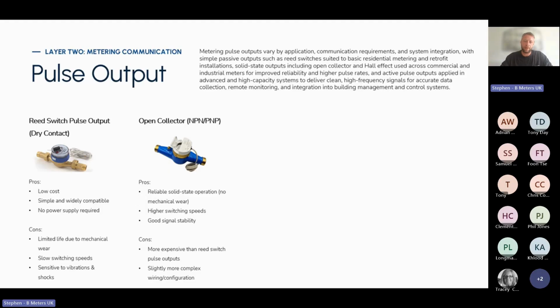More meters that you associate with the utility markets around Europe, such as BMeters, Itron, Elster, where they have a pulse output, it's an open collector pulse output. And the pros of the open collector run in the face of the cons of the reed switch pulse output. Reed switch pulse outputs have limited life due to mechanical wear, slow switching speed, and are sensitive to vibrations and shocks. Ultimately, if data is important, the reed switch pulse output is just not going to cut it long term. It will work, it will serve a purpose, and it's very easy to work with, but it won't give you reliability over the length of the meter.